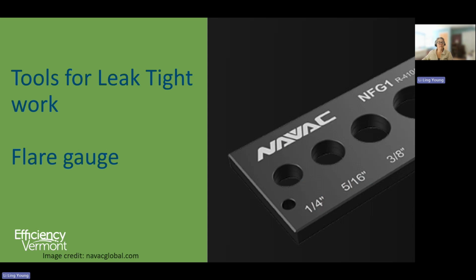This is a flare gauge. Inside each hole is a little tiny lip. So if the flare fits in the hole and lands on the lip, the flare is the right size. But if the flare drops through the hole, it's too small. So check all of your flares with the flare gauge.